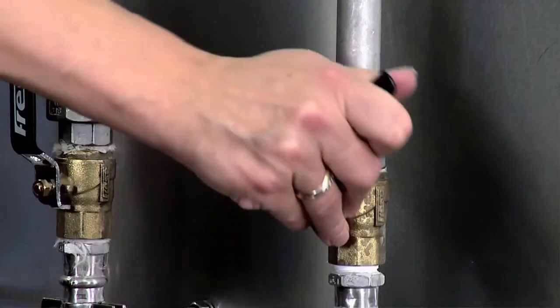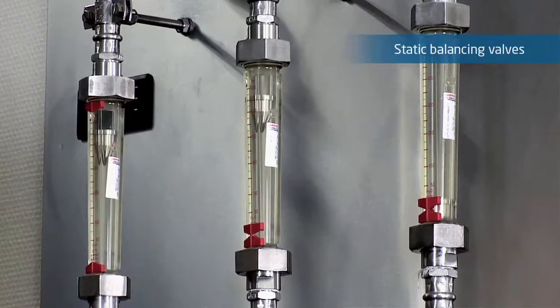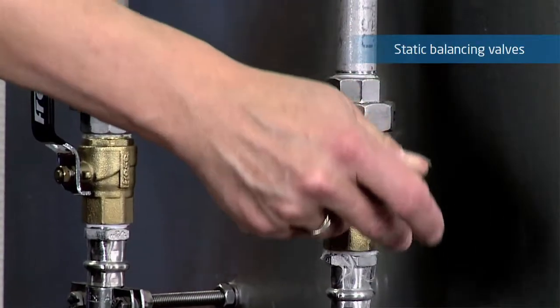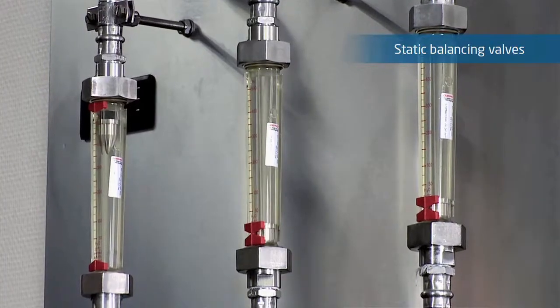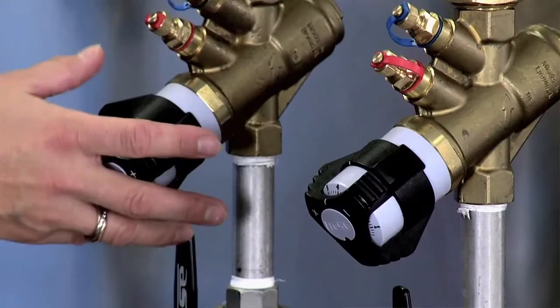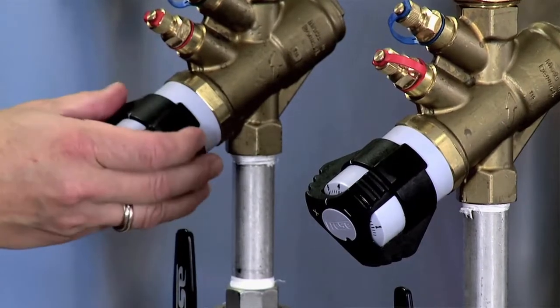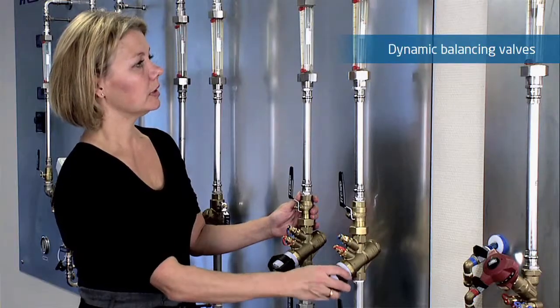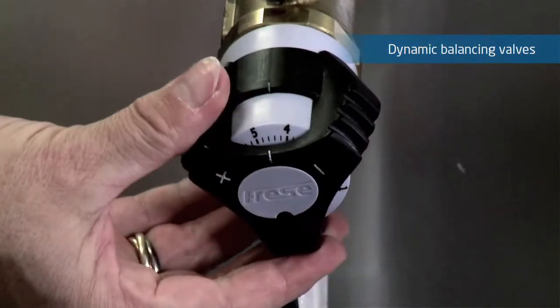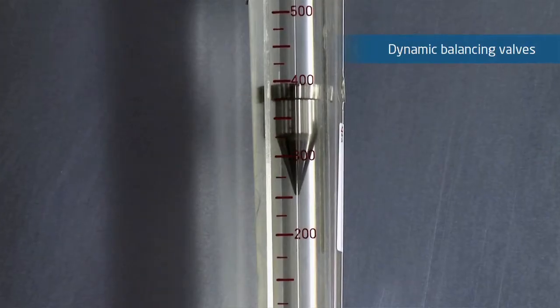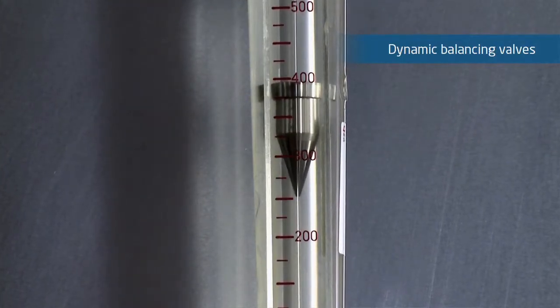The problem though is that the pumps speeding up and slowing down, and the valves opening and closing, causes all kinds of chaos in the pipe system. We need what we call pressure independent devices, which can increase or decrease their characteristics or resistance to control flow around the building effectively and efficiently.